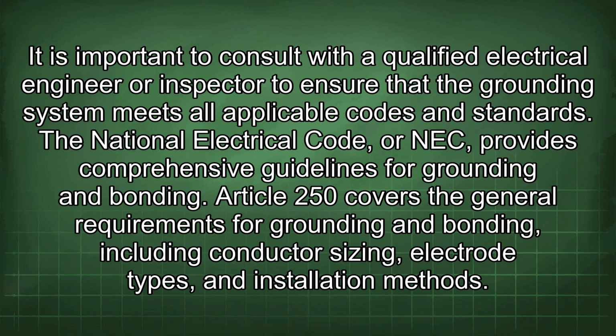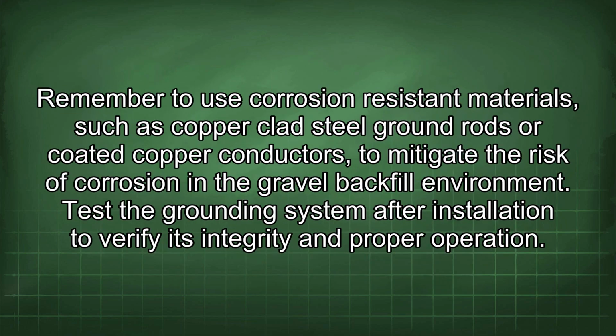The National Electrical Code, or NEC, provides comprehensive guidelines for grounding and bonding. Article 250 covers the general requirements for grounding and bonding, including conductor sizing, electrode types, and installation methods. Remember to use corrosion-resistant materials such as copper-clad steel ground rods or coated copper conductors to mitigate the risk of corrosion in the gravel backfill environment.